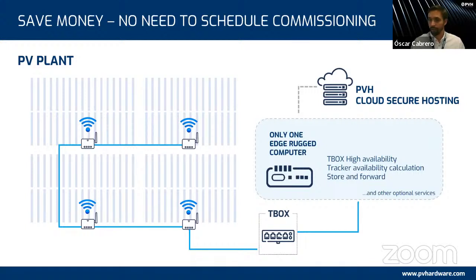That edge rugged computer is the key device to perform what we call T-box high availability, which is the secondary redundancy in our system. The first was communication redundancy, and with ProInsights we also offer T-box high availability, a virtual system continuously watching over the T-box. Whenever a T-box fails, another instance is instantly created on that edge rugged computer to keep performing the control task, giving the operator time to replace the damaged device. Then this virtual instance will be reset onto the hardware T-box.